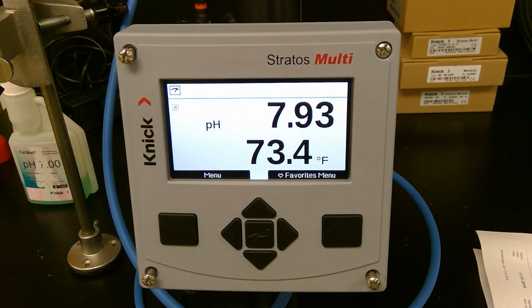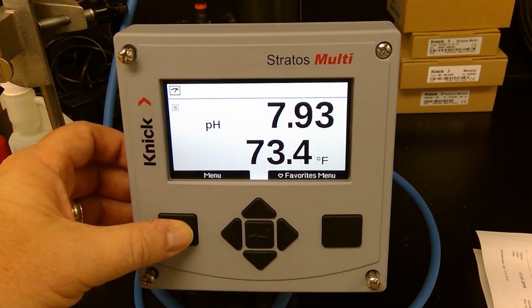Now, if it's already in process, you can assume that it's already hydrated, but if you're going to put it in for the first time, you want to soak it overnight in a buffer 7. That way, when you go to put it in and you do your process cal, it won't drift as it rehydrates. But for this video, we're going to assume it's already been in process or soaking overnight. So we're going to go ahead and proceed with that product calibration or PCal.